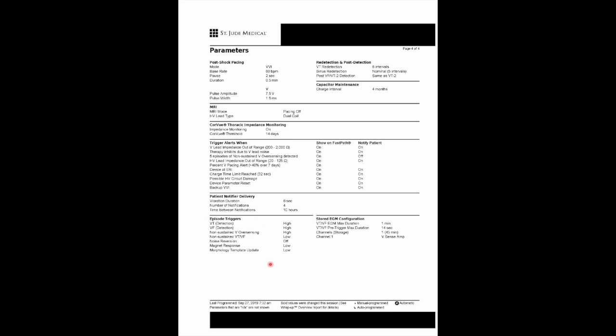Here you can customize episode triggers. So if you're getting a lot of, let's say, magnet responses, or you don't want these morphology templates, you can certainly turn those off. You can also go into your stored EGM configuration. One thing I like to do is on this pre-trigger, I like to go to 20 seconds. I really want to see how an episode starts. I think that's super important. Is it a PVC that's kicking off something, or what is it that is triggering that episode? So I will change this. It is nominally 14 seconds. Oftentimes I do change that to 20 seconds.